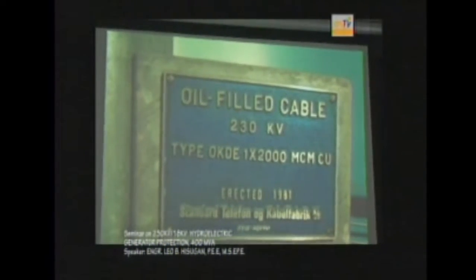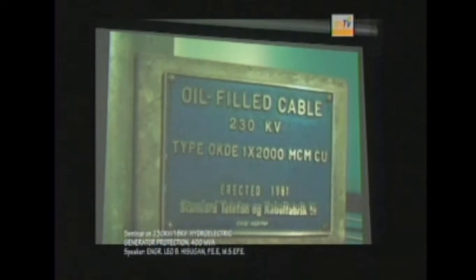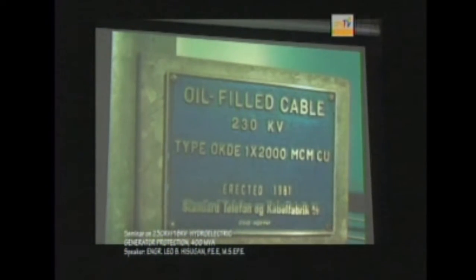The first single line diagram, we have that we're using an oil-filled cable. The 230 kV cable is 2000 MCM copper, and we buy this directly from Oslo, Norway. I think the cost of the cables, like maybe there's 9 of them, is like $1 million US, just the cable alone, 1,500 feet, oil-filled cables.